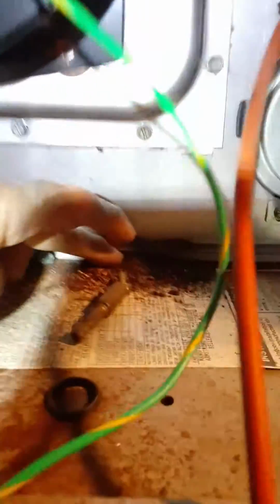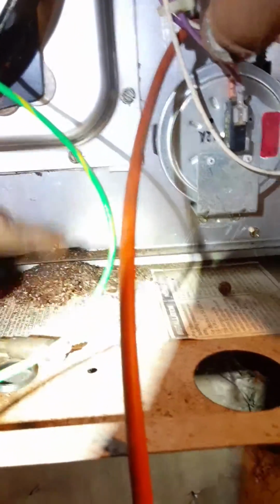This one did have a lot of rust. When I pulled this chamber out, see all the rust down there. Tells me that the heat exchanger isn't draining fast enough, or they've got a lot of condensate. So furnaces don't last a long time when they're rusting out like that.